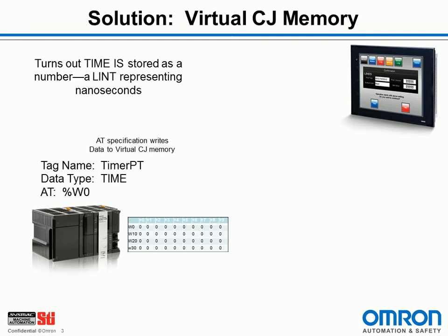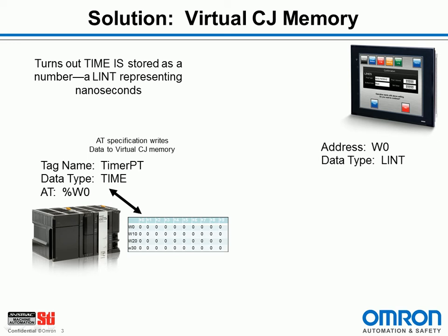By doing that, that now sticks the memory for that variable into the CJ memory. On the HMI, instead of putting in the tag name now, I can put in the CJ address. And now the data type of long integer doesn't check to see that time equals long integer. It just reads the eight bytes out of work area word zero and it just imputes the long integer data type to it. And so everything actually works quite nicely.